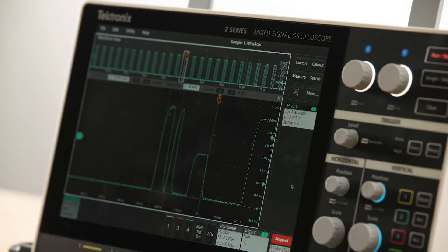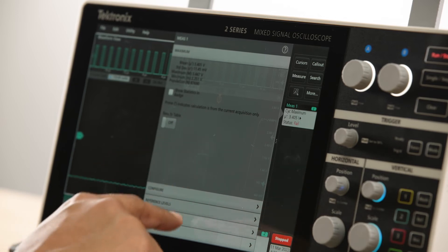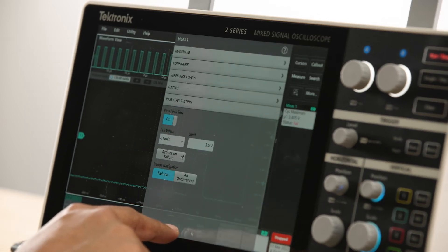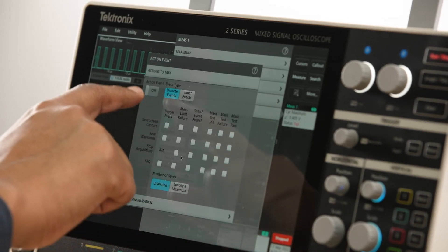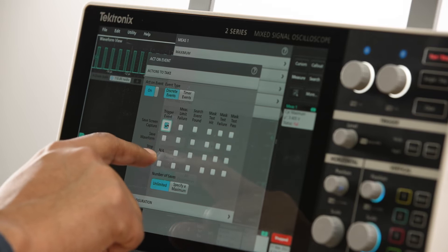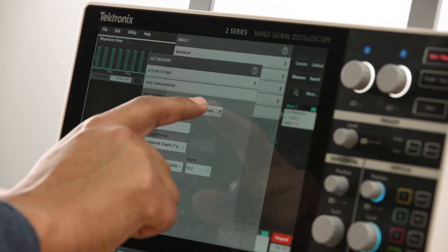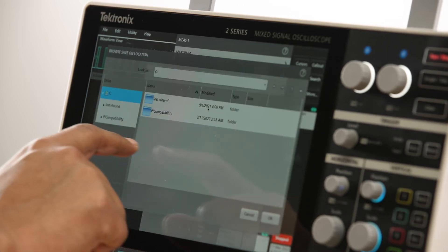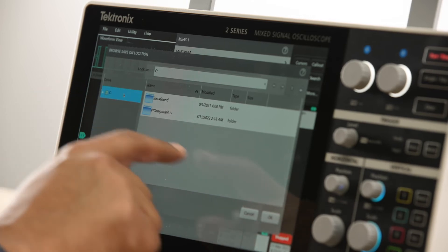The act-on event feature built into the 2 Series MSO can be used to set up the oscilloscope to respond to events such as trigger, measurement limit failures, search, or mask measurement failures.